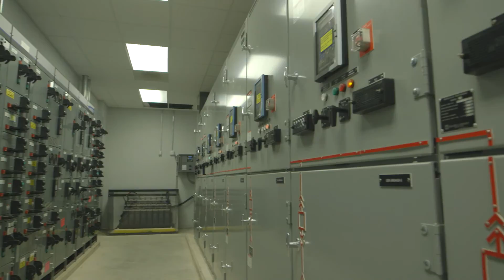Okay, the room you just passed through, that is our electrical switchgear room, and that is where motor protection takes place, and also the 4 kV switchgear from the generators. The 4 kV switchgear controls that, and it comes out here to the step-up transformer. And the step-up transformer takes it from 4160 to 34,500 volts. That's a common transmission voltage, and that allows us to transmit the power the 6 miles to the substation.